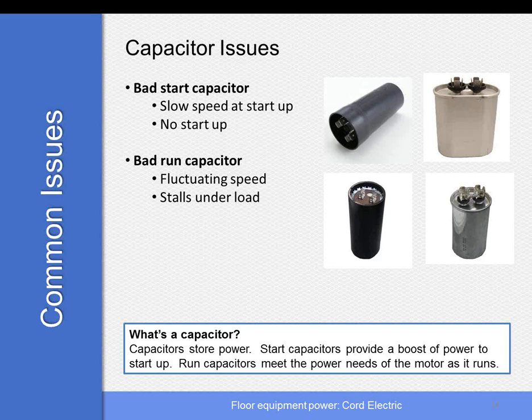So the symptoms of a bad start capacitor is it's going to be really slow to start, and it may not even start at all. A bad run capacitor is probably going to waver in speed up and down the motor, and it could even stall the motor.